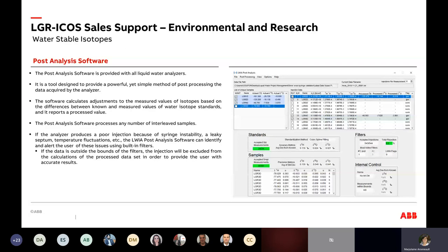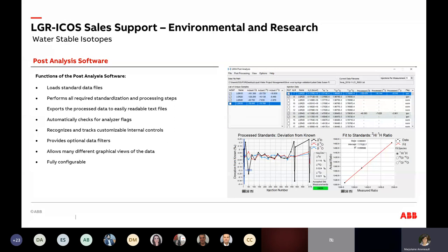A great feature of the liquid system is the post-analysis software. All calculations are done automatically — known and unknown concentrations are entered and calculated, so the operator doesn't have to perform any manual calculations. The software also produces flags for issues such as syringe instability, septum leaks, temperature fluctuation, or contaminants. There are many graphs, options to export and customize. We'll cover this in more detail with specific examples in the upcoming presentations on hydrology and biology studies.